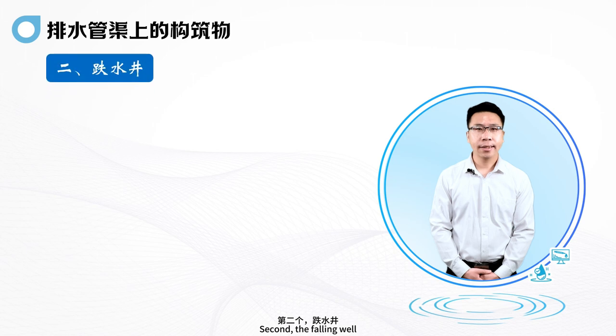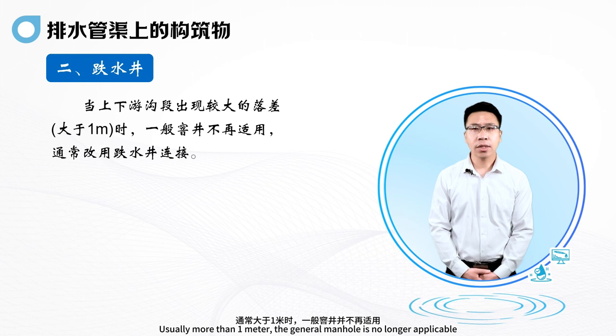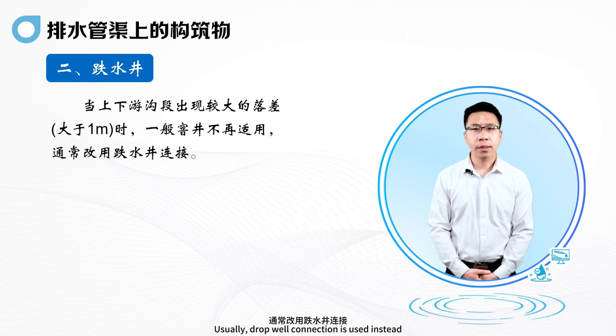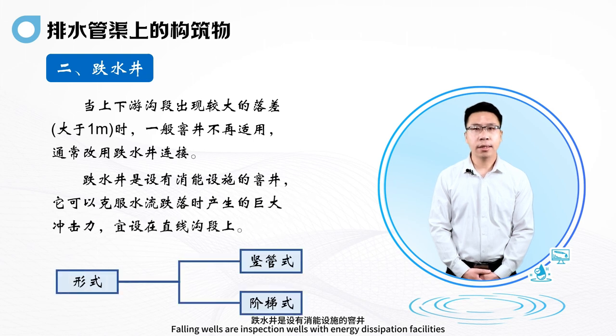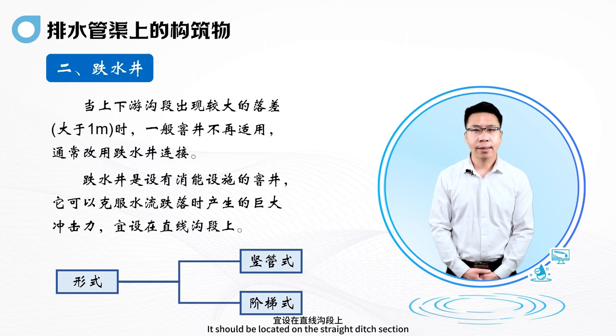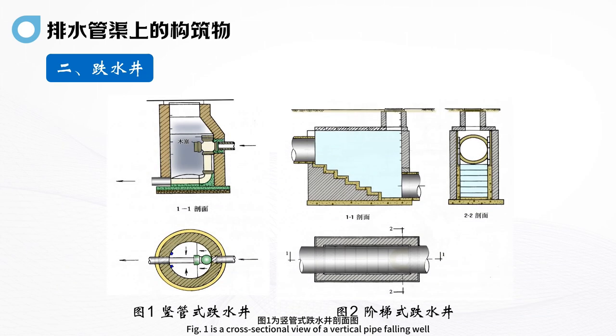Second, the falling well. When there is a large gap between upstream and downstream ditches — usually more than one meter — the general manhole is no longer applicable, and drop well connection is used instead. Falling wells are inspection wells with energy dissipation facilities that can overcome the huge impact force when water flow falls. It should be located on the straight ditch section. Forms of falling wells include vertical pipe type and stepped type. Figure one is a cross-sectional view of a vertical pipe falling well; Figure two is a schematic diagram of a stepped falling well.